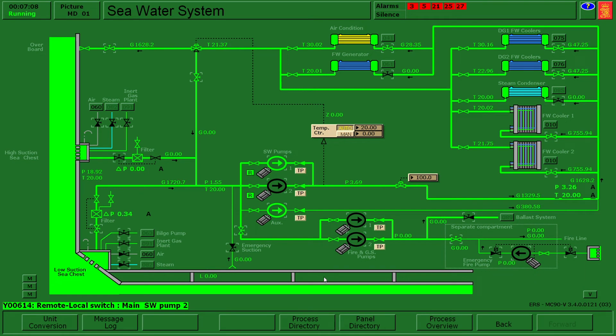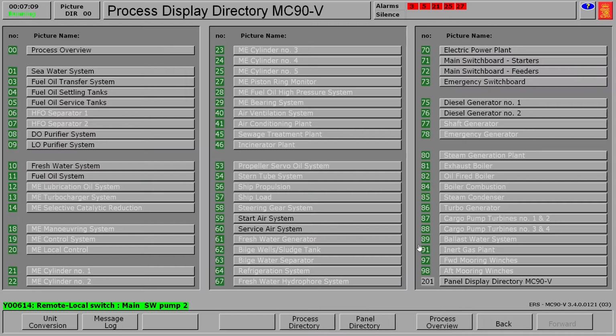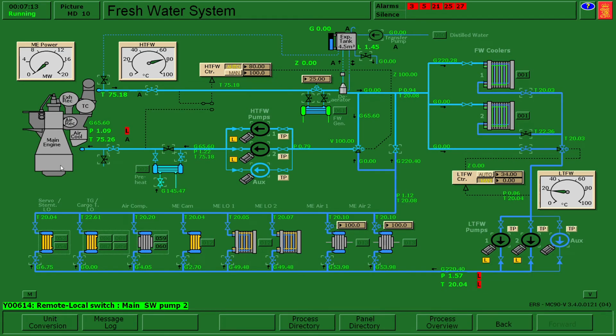And then after that, we're gonna go to MD10, which is our freshwater system. And then we're just gonna open up our bypass valve. We're gonna start our main pump number 1. Set the remote again, both pumps. Open this main pump as well. Set the remote as well.